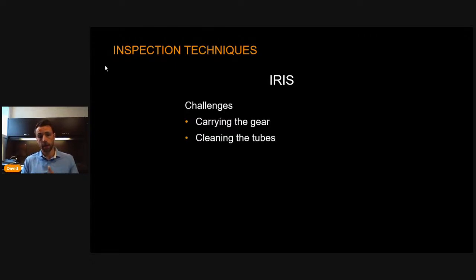Second, we've got tube cleanliness. To inspect those tubes, sometimes there is corrosion inside, deposits, so we need to make sure they are clean. IRIS is the technique that requires the most cleaning. So for an asset owner, an inspection company getting there to do the inspection will face this, and it's quite a burden for some asset owners to do a proper cleaning for IRIS to be used.